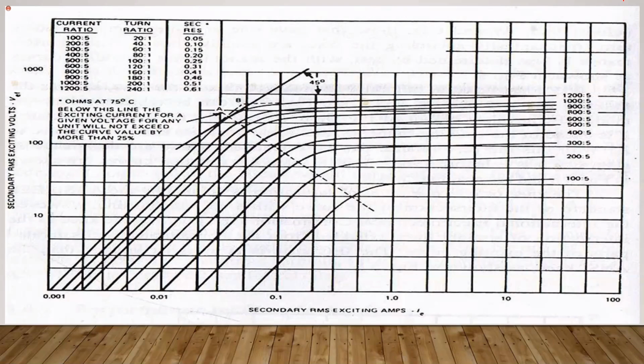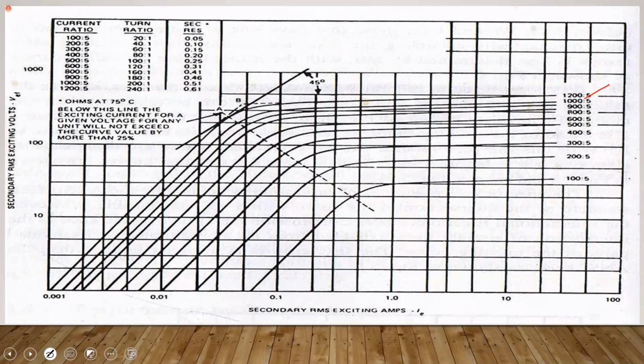Okay, so going back to what I was saying about the resistance, if you're on the 1200 to 5 tap, because you're using the full winding, it means that it will give you the greatest resistance, which is 0.61. If you're using the 300 to 5 tap, it means that you're using less of the winding. Okay? So what you have here is 0.15.